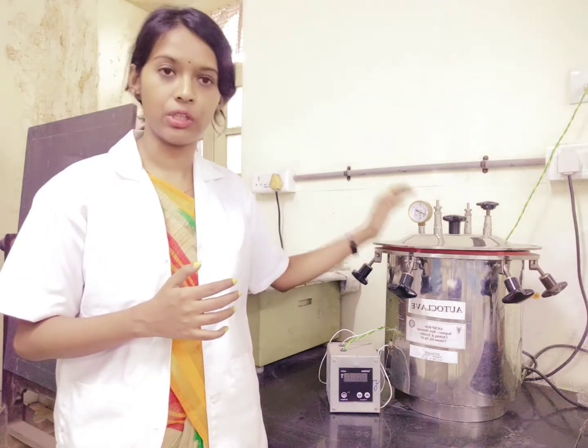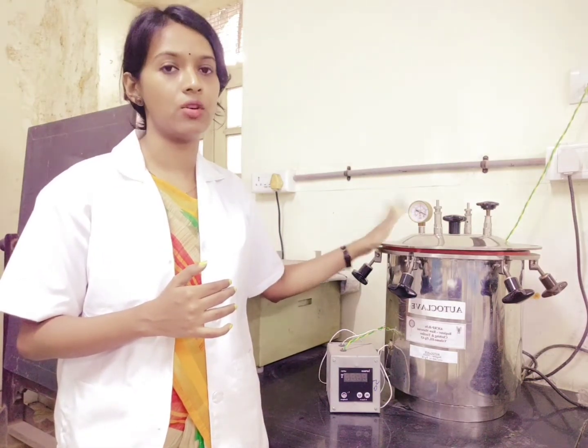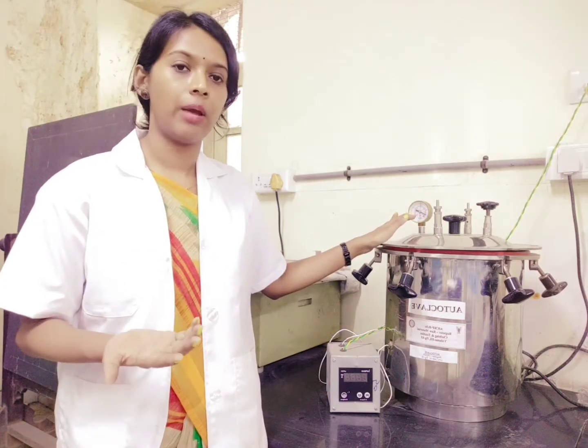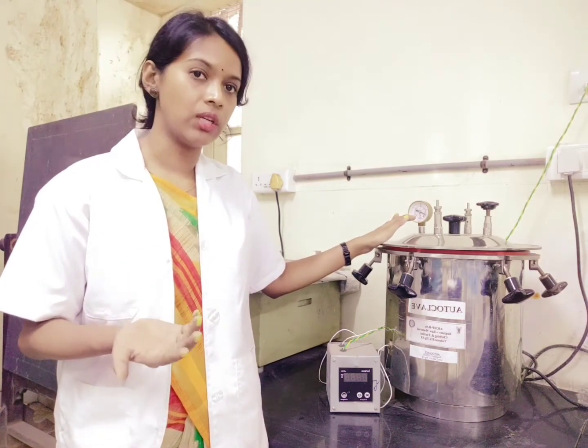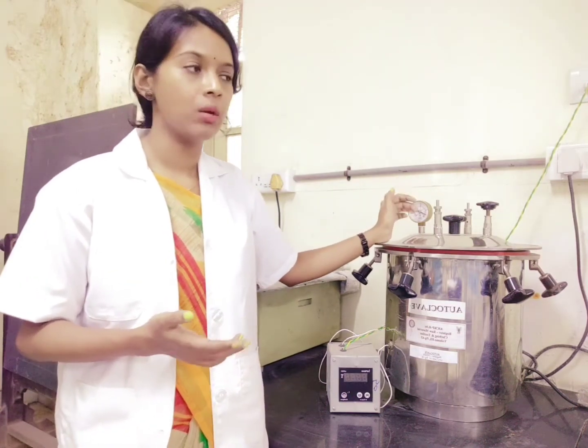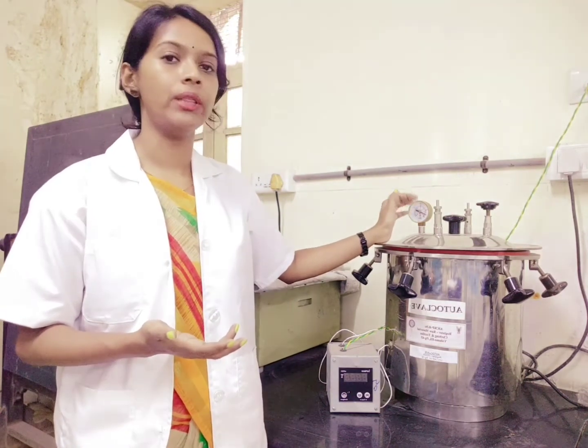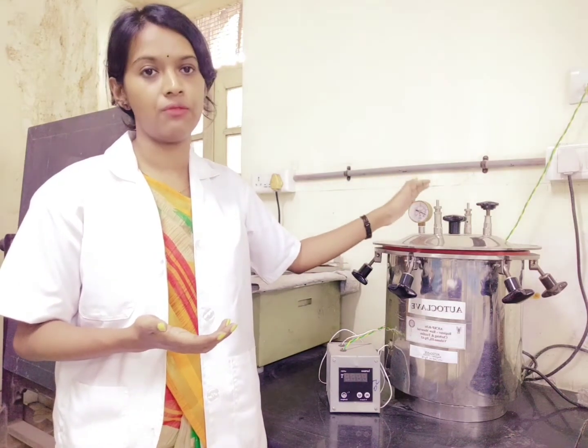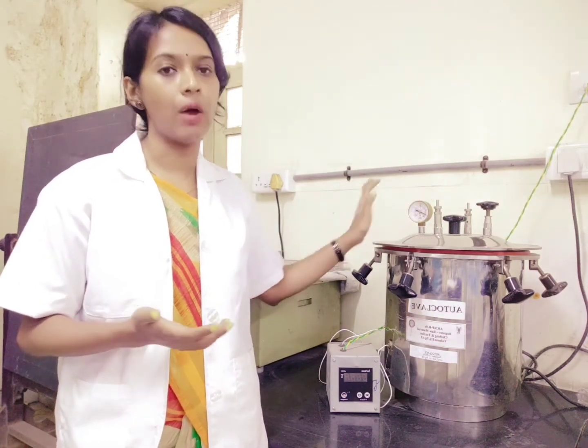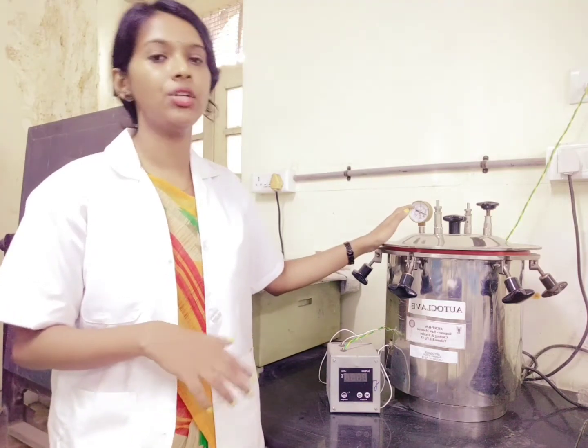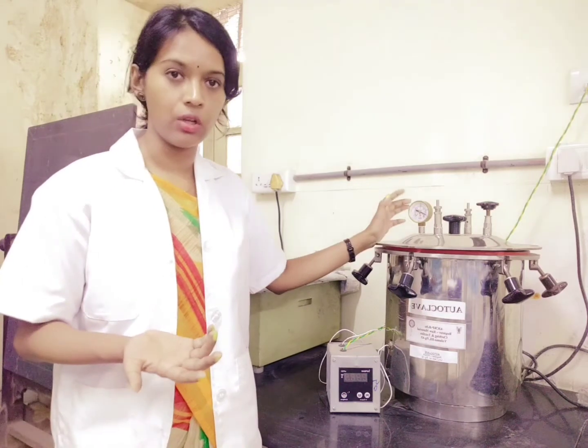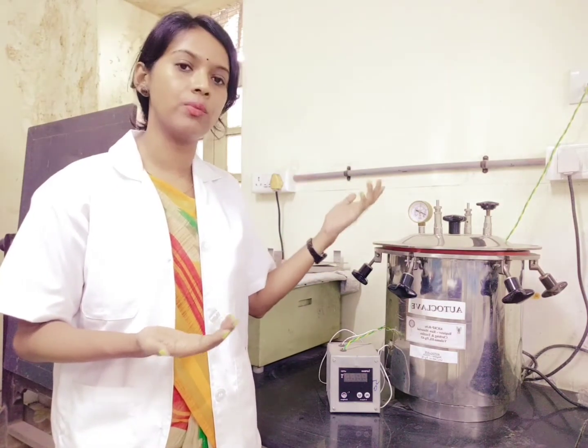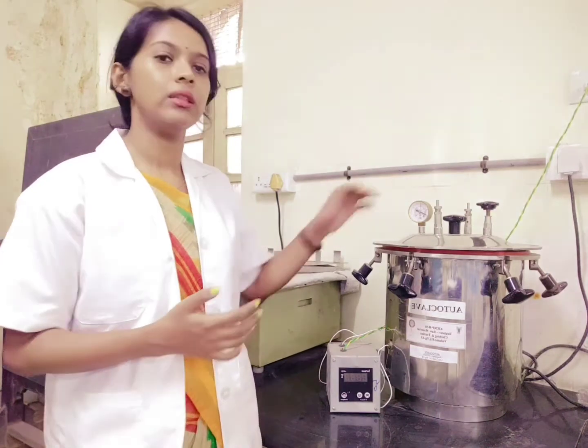That releasing of the pressure happens if the autoclave is automatic. In an automatic autoclave, when the temperature or the pressure reaches the set value, generally the temperature is set around 121 degrees and the pressure reaches 15 psi. PSI means pounds per square inch. So when the temperature is 121 and the pressure is 15, in that condition you keep the instrument for around 20 minutes, and after that you have to release the pressure. Then you turn off the instrument, and the pressure and the temperature will come down. That is for the manual one.